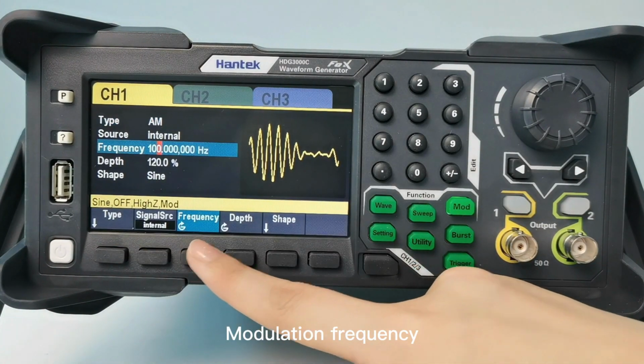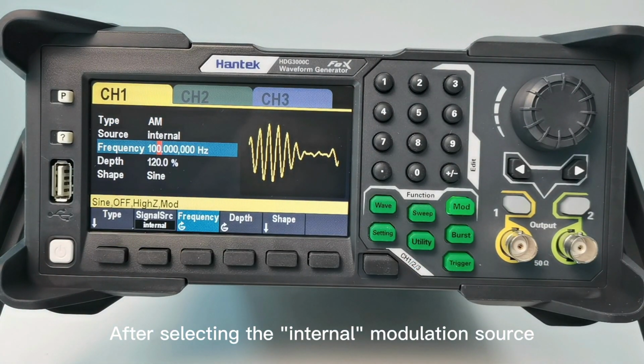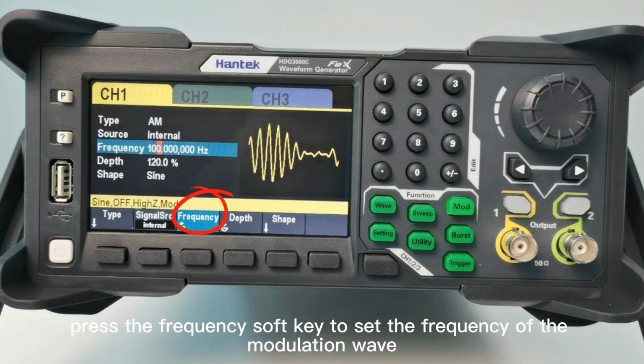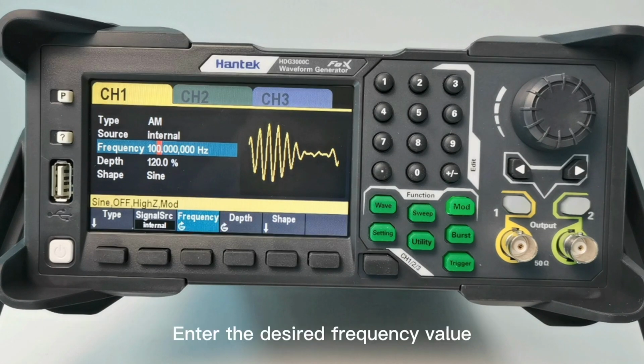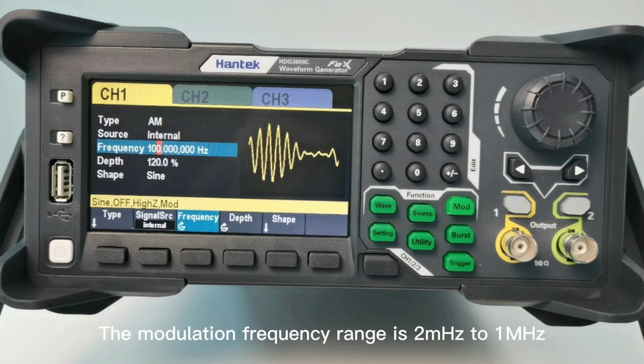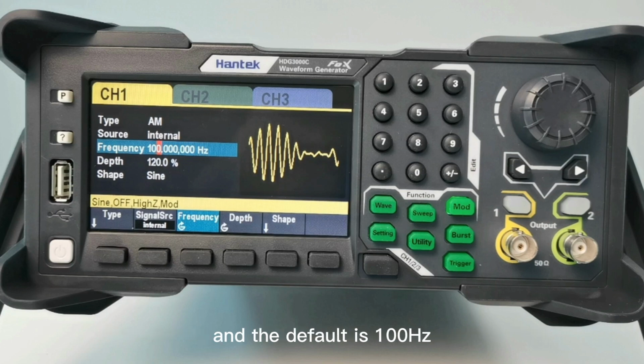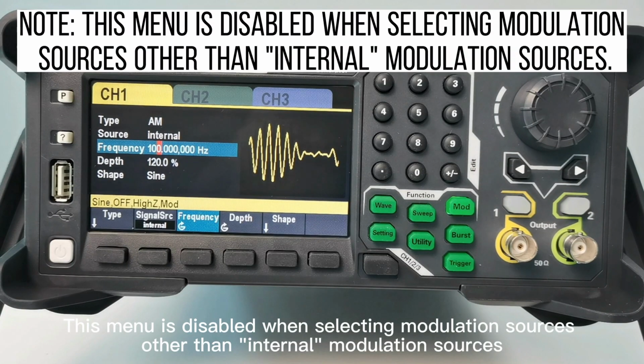Modulation frequency. After selecting the internal modulation source, press the frequency soft key to set the frequency of the modulation wave. Enter the desired frequency value. The modulation frequency ranges from 2 mHz to 1 MHz, and the default is 100 Hz. Note, this menu is disabled when selecting modulation sources other than internal modulation sources.